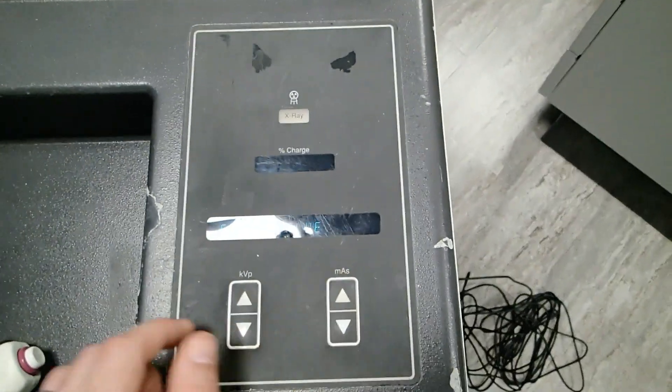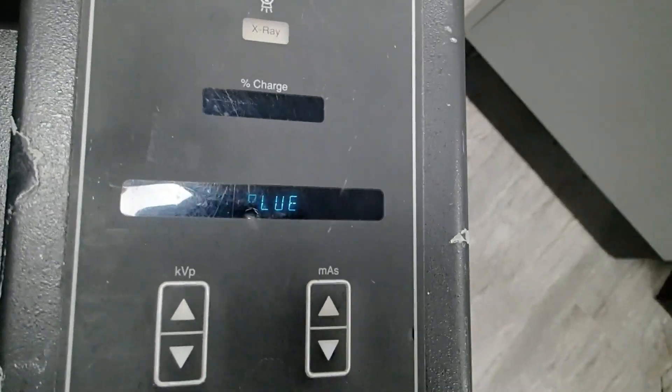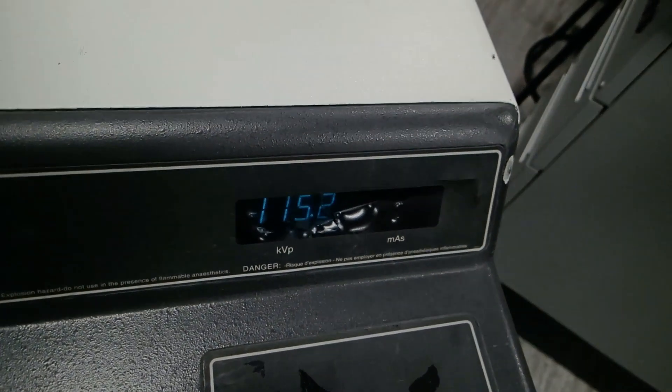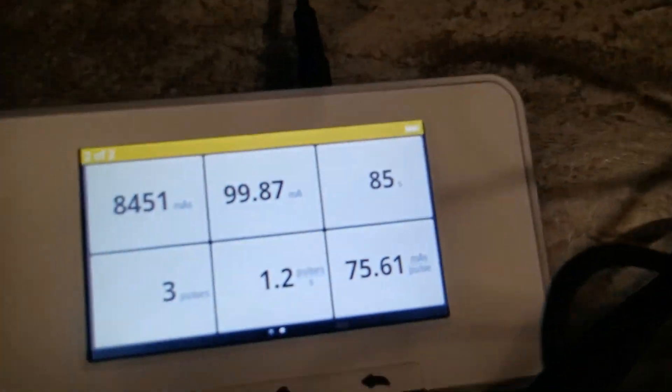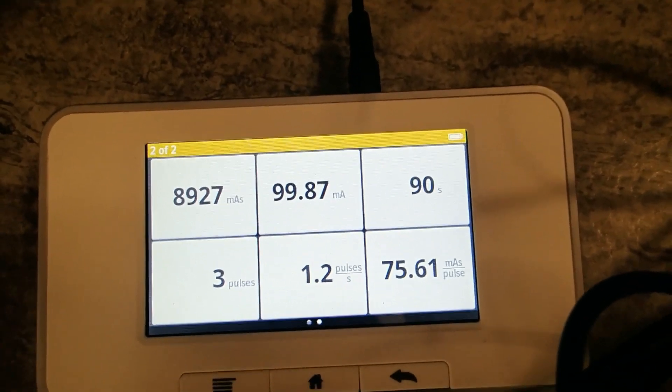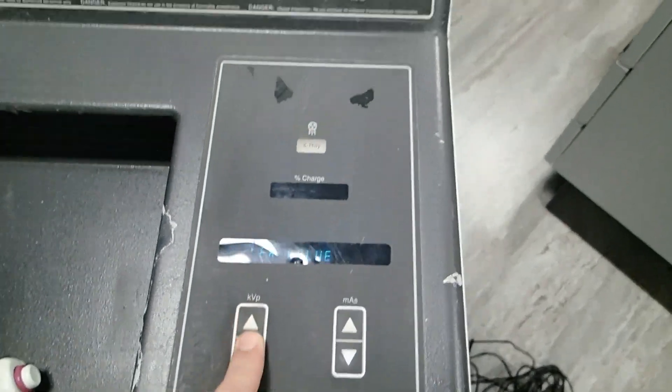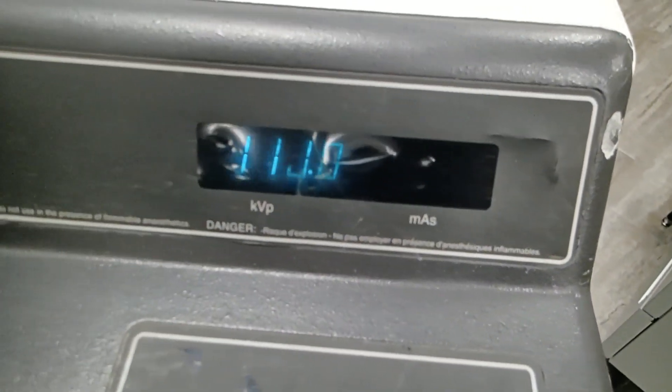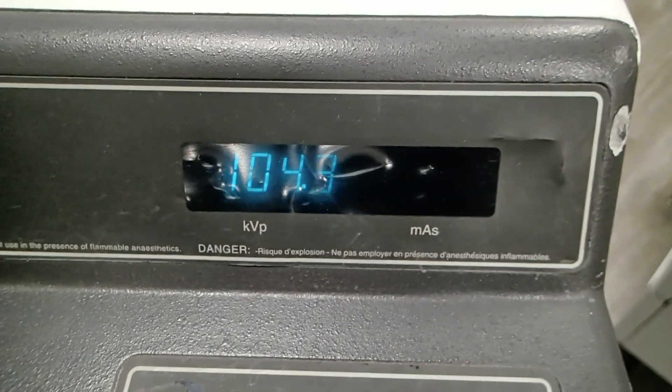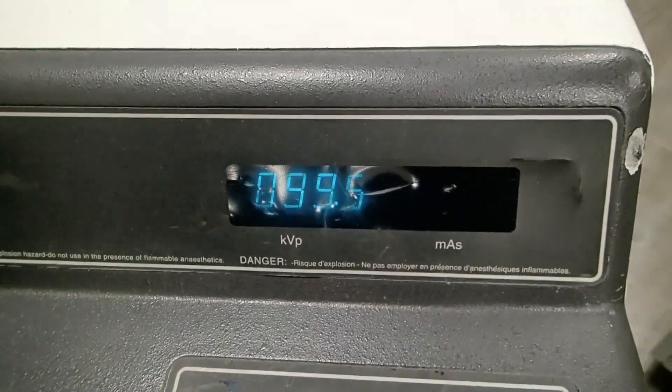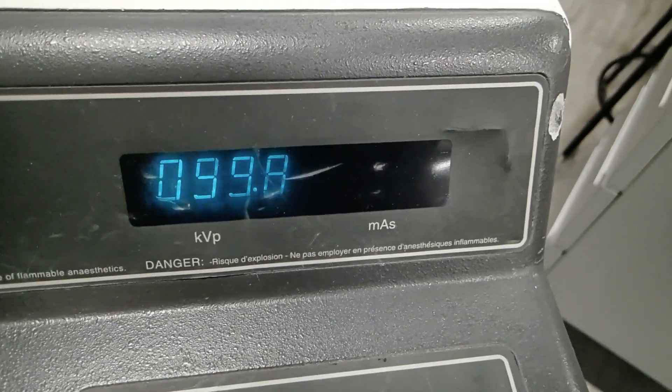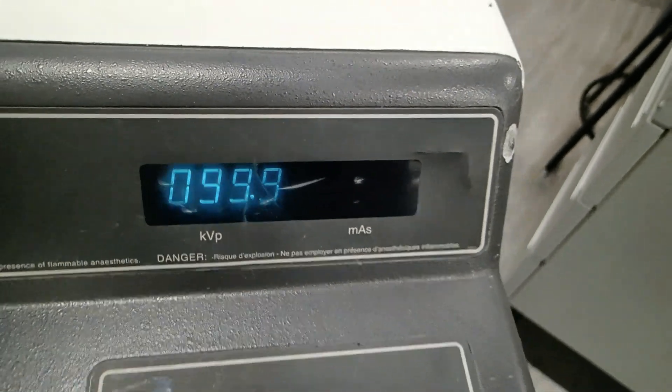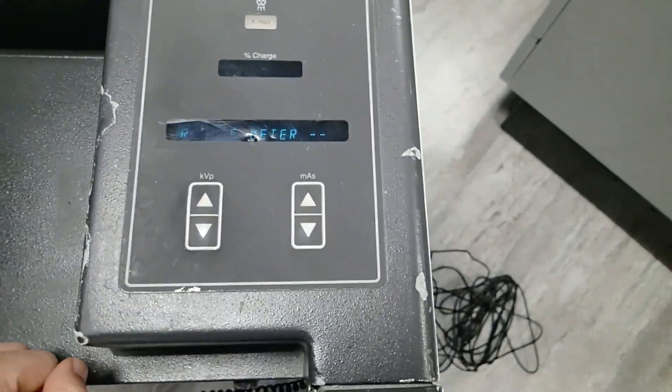I've gone ahead and pushed MAS up, and it goes to enter value. Now what we need to do is match the value on our AMX4 to the value of milliamps read on our meter. We're reading 99.87 milliamps on our meter. We need to enter that by selecting KVP up and KVP down. In this case I'm going to round up to 99.9 and I'm going to enter that value.